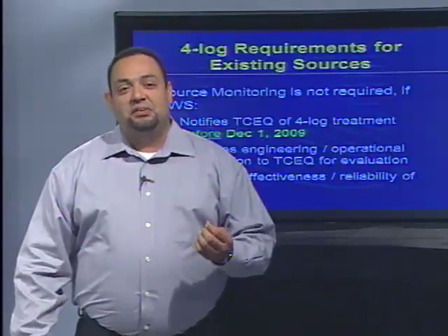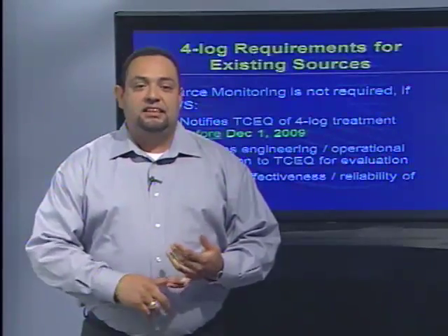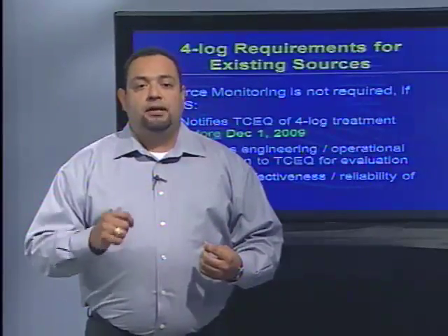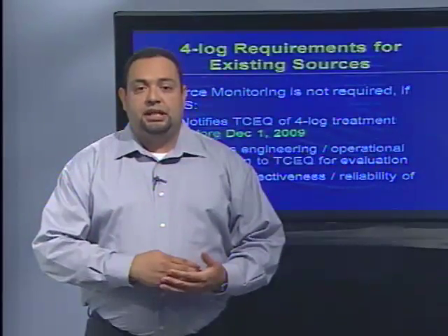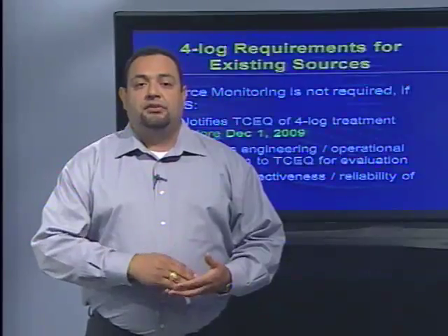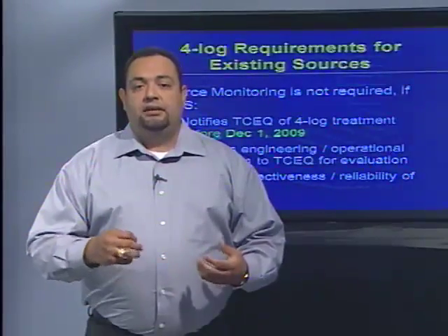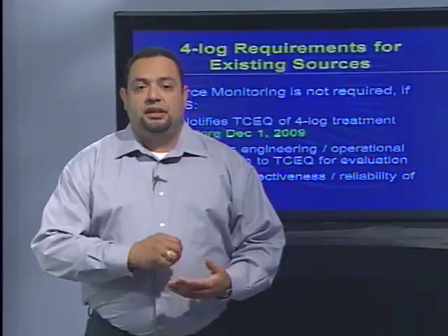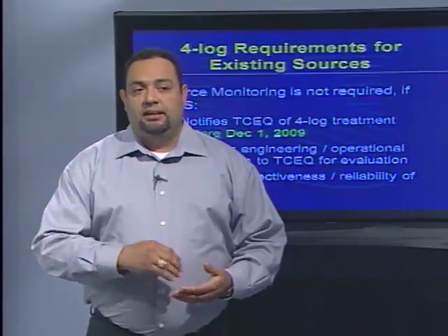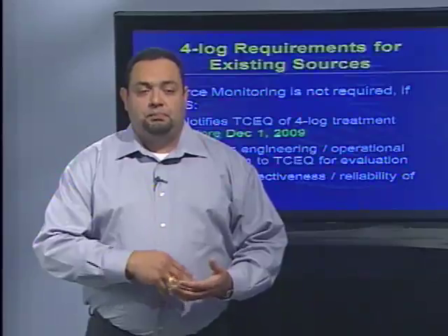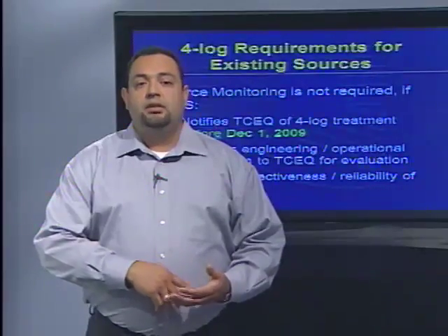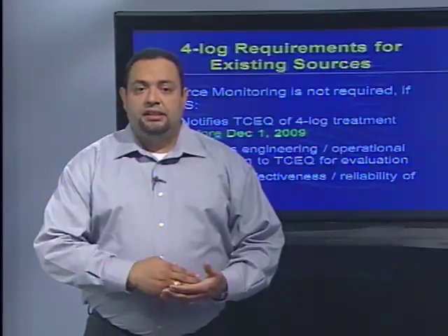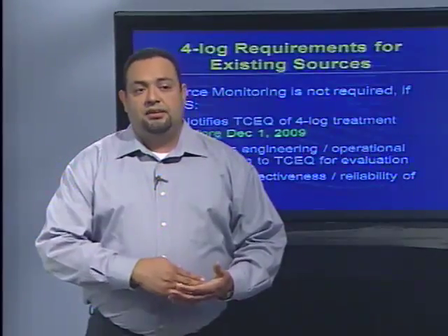And then also, you're going to want to monitor the effectiveness through the use of a worksheet called the Groundwater Monthly Operating Report. And you're going to want to use that sheet to calculate and make sure that you are abiding by that minimum specified residual, or what we call the MSR as well. So you're going to hear that term a lot. But again, the 4-log treatment is 99.99% removal or inactivation of viruses. And if you're going to use disinfection, that would mean inactivation of viruses.